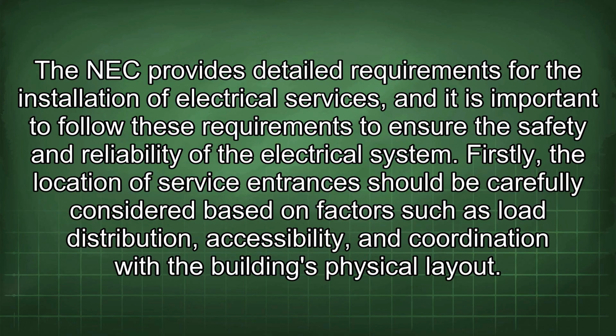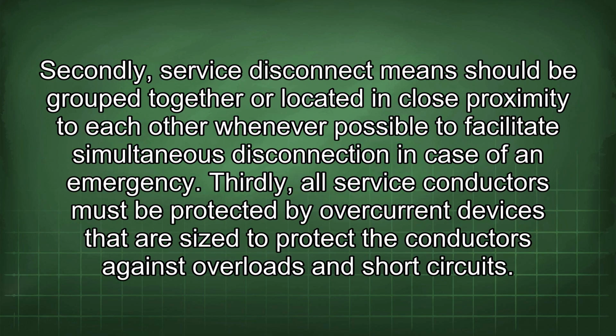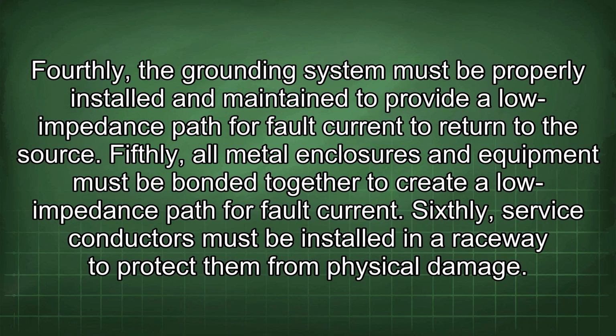Firstly, the location of service entrances should be carefully considered based on factors such as load distribution, accessibility, and coordination with the building's physical layout. Secondly, service disconnect means should be grouped together or located in close proximity to each other whenever possible to facilitate simultaneous disconnection in case of an emergency. Thirdly, all service conductors must be protected by overcurrent devices that are sized to protect the conductors against overloads and short circuits. Fourthly, the grounding system must be properly installed and maintained to provide a low impedance path for fault current to return to the source.